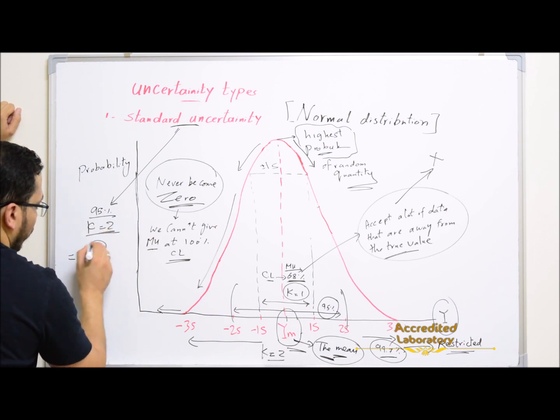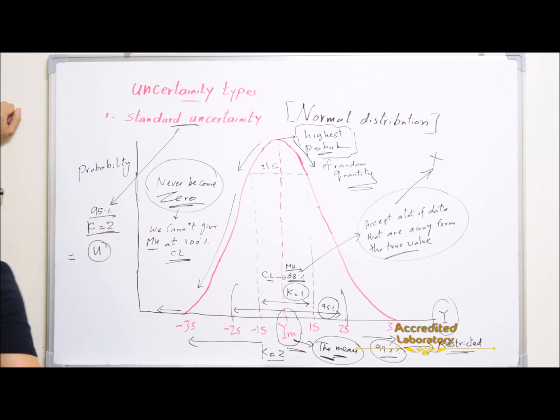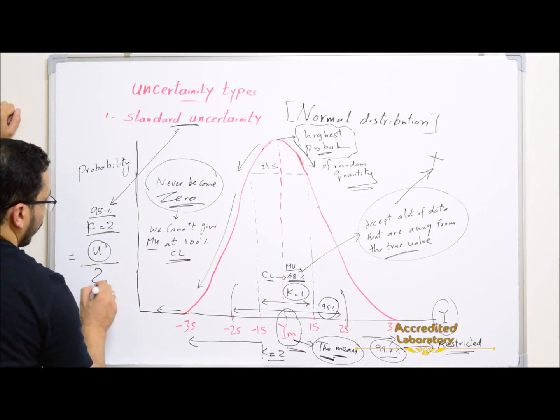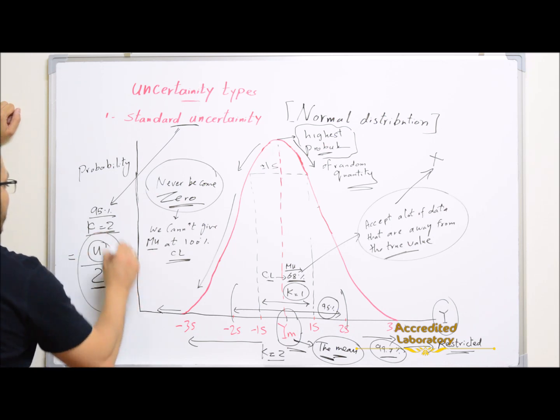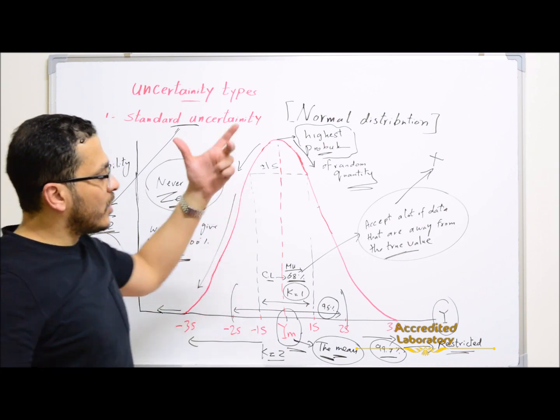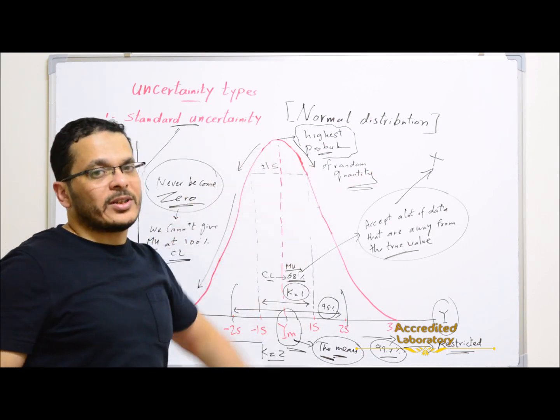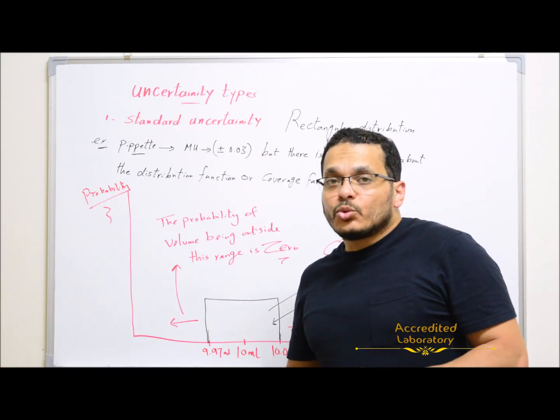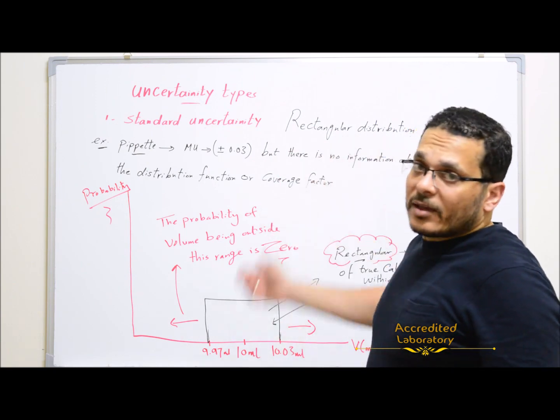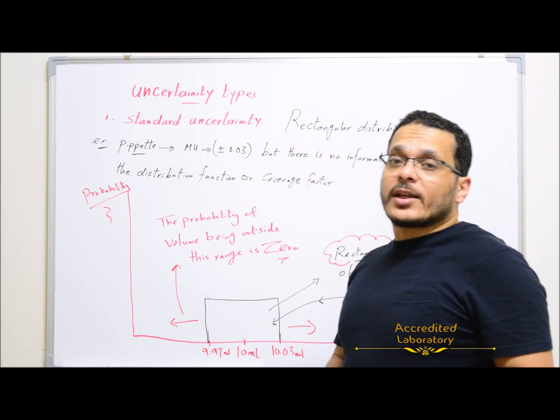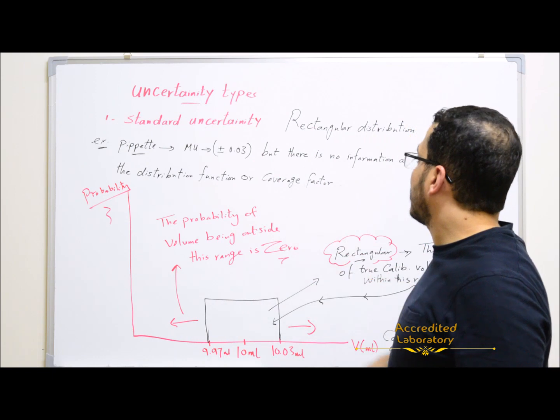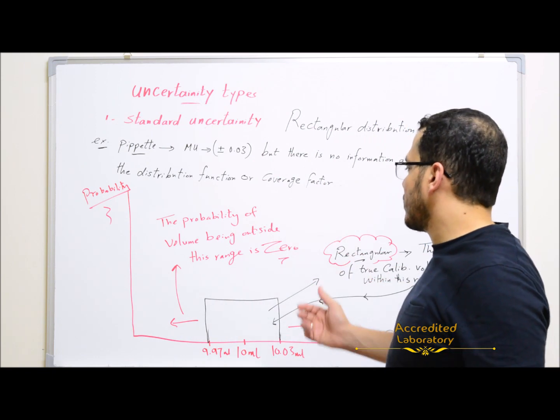You can assume that uncertainty coming from calibration certificates, like for balances or micropipettes, is normally distributed. In this case you calculate the standard uncertainty at 95% confidence level, which means coverage factor k equals 2, by dividing the uncertainty from the calibration certificate by 2. This gives you the standard uncertainty using the normal distribution.